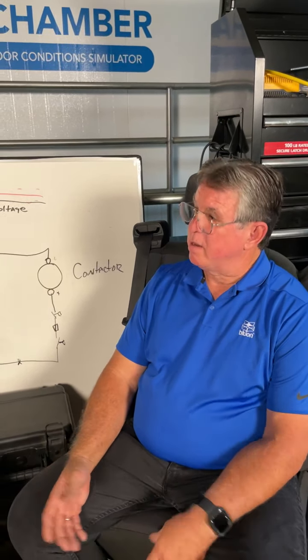There are other things that go into that as well. If you've got quite a hike because you can't hear the condensing unit, or you're not going to be able to go and feel the line and feel if the refrigerant's flowing in a short amount of time, we say jumper from R to Y, but if you're going to be running it for a while, make sure you turn the daggone fan on. That's R to G. Yeah, because if you pull the subbase, it ain't gonna help. So you need to make sure that the indoor fan is running if that compressor is going to be running for any length of time, because all of this is making sure we don't break a compressor.